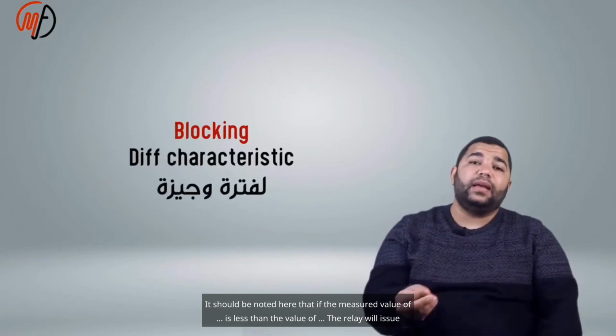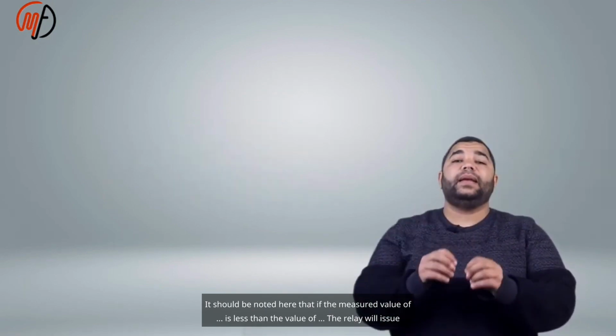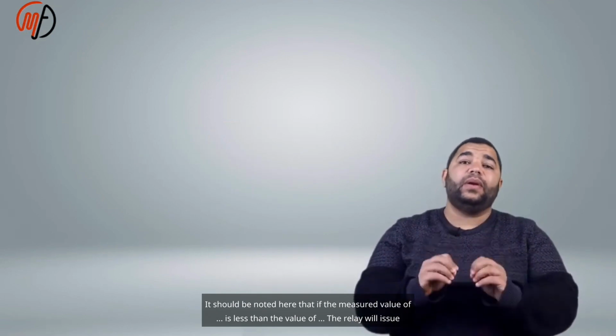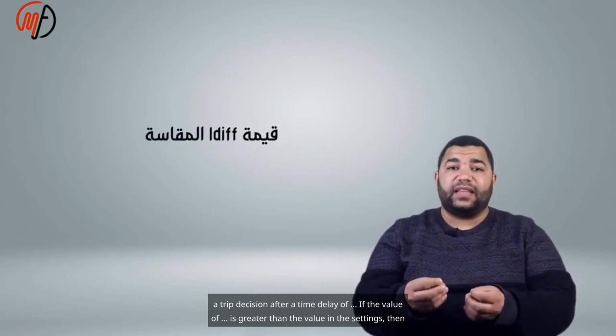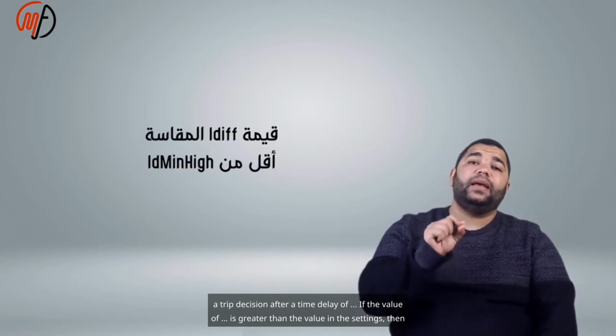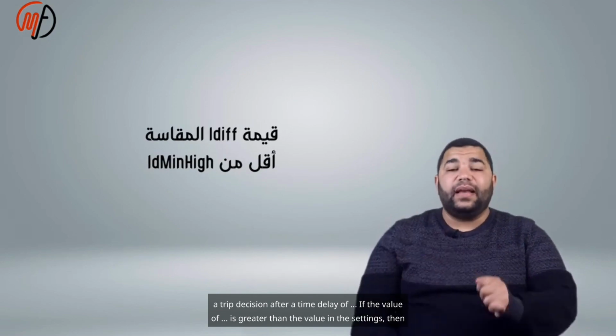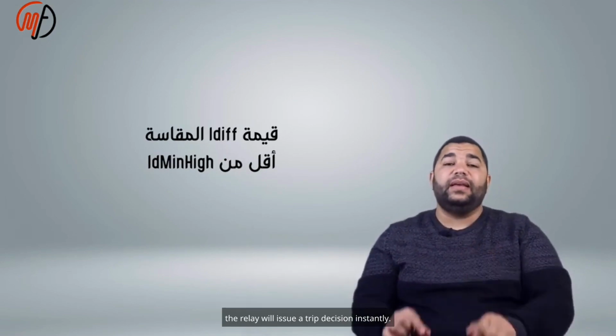It should be noted here that if the measured value is less than the set value, the relay will issue a trip decision after a time delay. If the measured value is greater than the value in the settings, then the relay will issue a trip decision instantly.